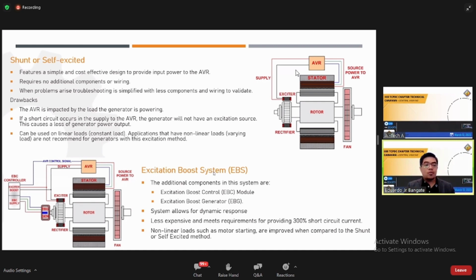Okay? If a short circuit occurs in the supply to the AVR, the generator will not have an excitation source. This causes a loss of generator power output. This type of excitation method can be used on linear loads and constant load applications, but it is not recommended for non-linear loads and varying loads. So what does that mean? We have linear loads. Everybody knows the linear loads and the non-linear loads. The non-linear loads are those that possess harmonics, because they will draw more current from the generator.